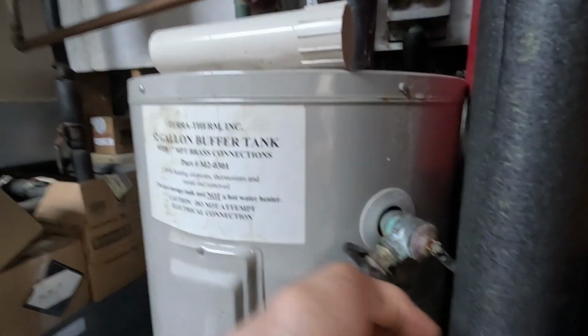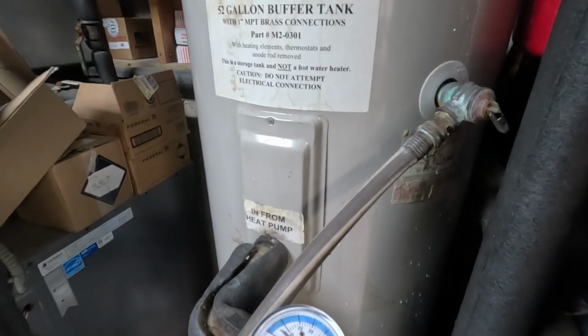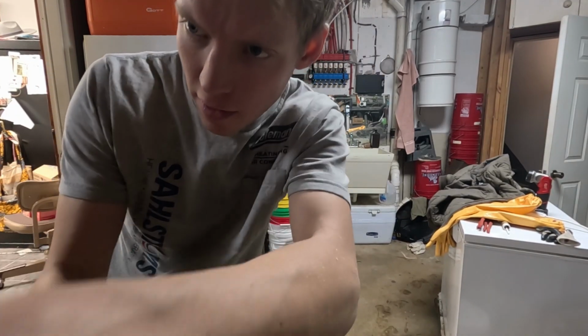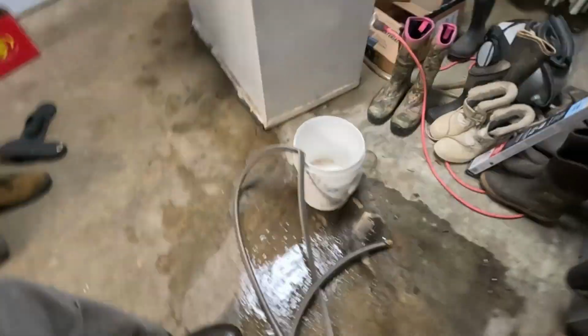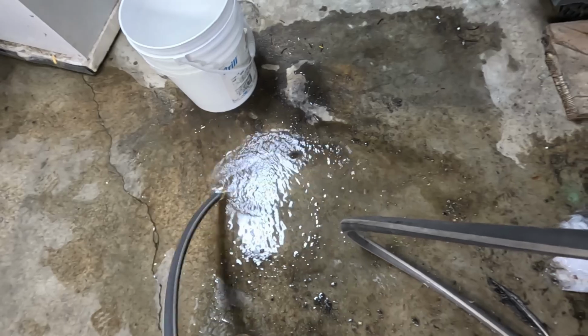It's almost down to 0 already, but I can rinse the mud that I tracked in here down the drain. I'm kind of curious if this opened up from the heating part, like if it got up to 210 and then melted that stuff out, because I doubt that it got up to 150 psi. So that's actually kind of an interesting fault. I've never had one fail from the temperature being overreached. It appears the pressure is pretty much down.